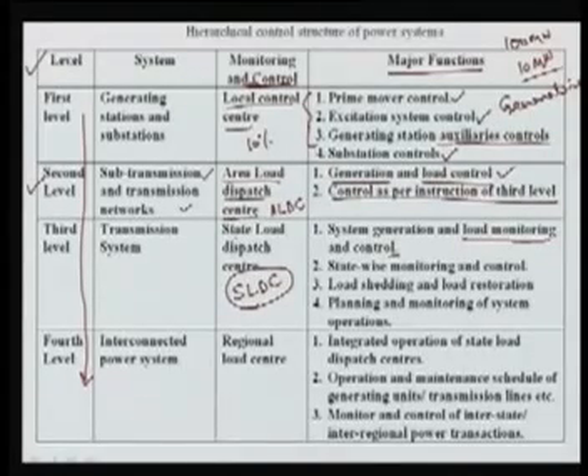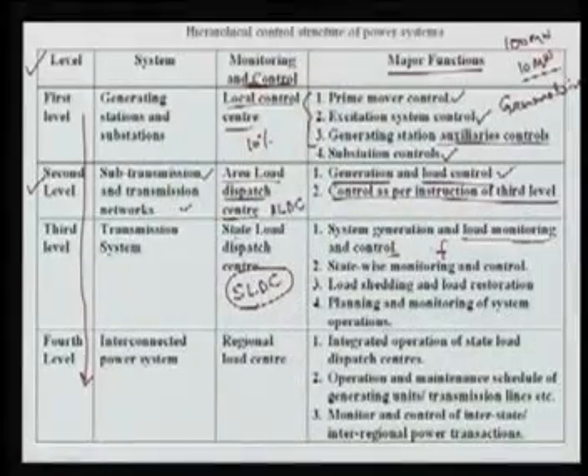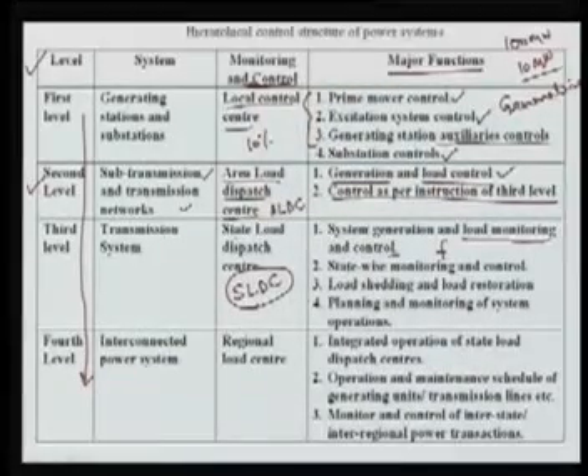If they are unable to, then they are going to set the load accordingly, so that the load and generation can be balanced. Basically here in our state, since we are always suffering from a crisis of power, they are going to look at load management, because the generation is normally at its maximum level. So we are basically controlling the load so that we can match generation and load to maintain the frequency of the system. They normally look at the frequency. If the frequency is 50 Hz, they are very happy. If the frequency falls, they are very worried, and they will go for load shedding so that they can improve the frequency of the system. So these are the functions regarding state-wise monitoring and control.